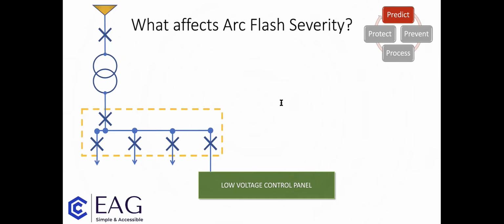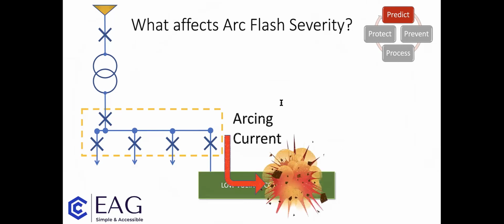So what affects arc flash severity? Well, there are 2 things initially. So if we're looking at this network here, feeding a low voltage control panel, the first thing that affects arc flash severity is the arcing current, and that's determined by the fault current upstream and the voltage and so on to provide the arcing current. And as I mentioned incident energy earlier, there's a direct relationship between arcing current and the amount of incident energy that's derived from an arc as a result.